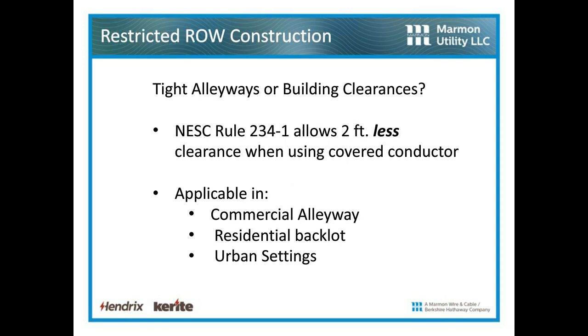So if we've got tight alleyways or building clearances where we really don't have enough space, the National Electric Safety Code modified Rule 234 in 1987. That rule requires 7.5 feet to the building side for a bare wire construction. Now it allows 2 feet less when using a proper covered conductor, so 5.5 feet.